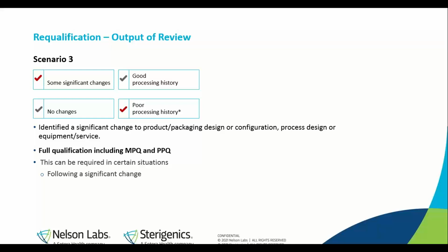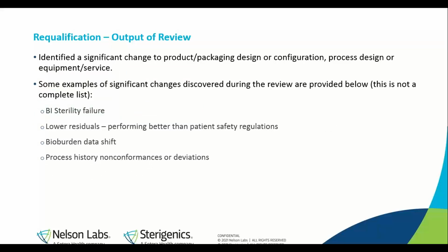Once again, this can be required in certain situations following a significant change. If you have identified a significant change, some examples of such a change discovered during the review are provided below, and this is certainly not a complete list. So some examples of this would be a BI sterility failure, a need to observe lower residuals that perform better than the patient safety regulations as they exist, a bioburden data shift, or process history nonconformances or deviation.